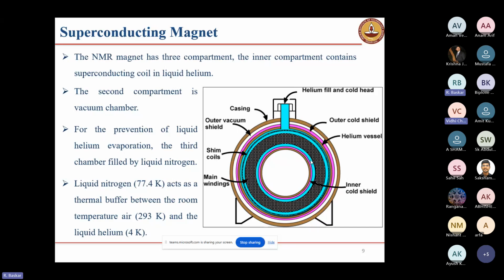Liquid nitrogen filling is most important, ma'am. Based on how you maintain the liquid nitrogen level, the liquid helium hold time will increase. Another question related to the liquid nitrogen: in our general practice, we fill the liquid nitrogen when it comes to almost 50% level. Actually the helium evaporation will be more then, ma'am, so at least try to fill weekly once. Don't wait for 50%. In our general practice, we fill weekly.